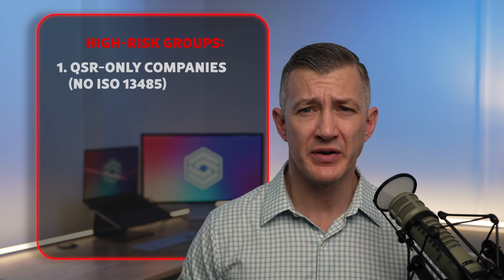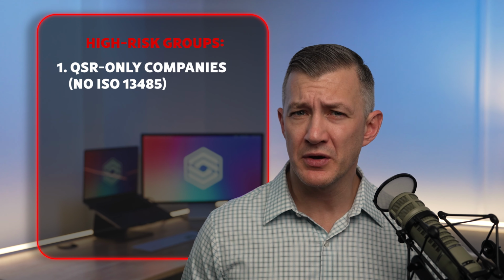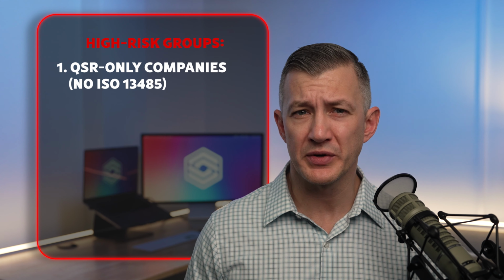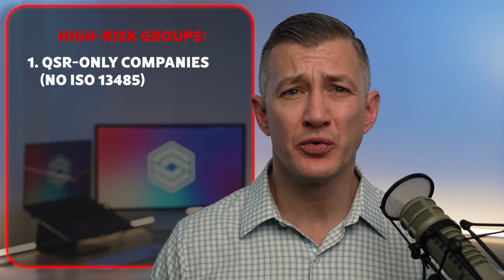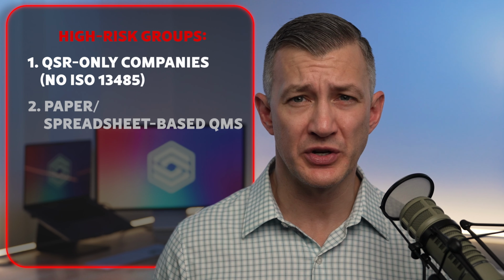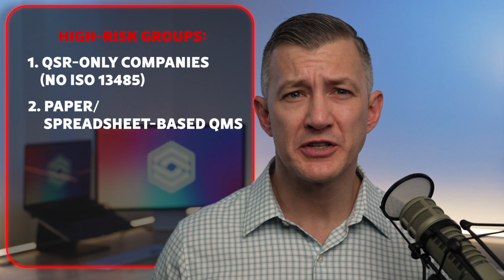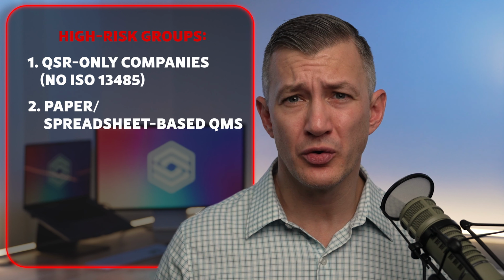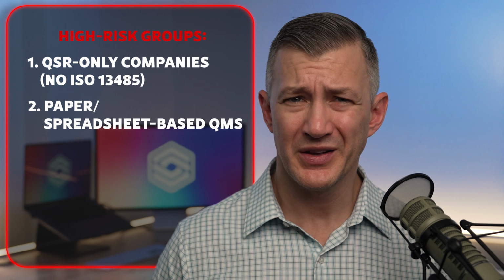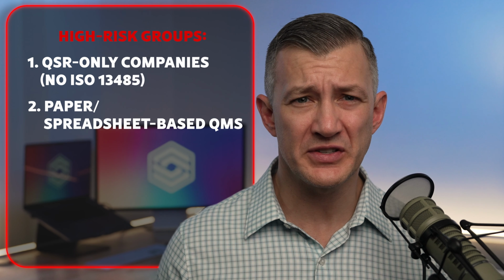So the question becomes, who's most exposed? The most high-risk manufacturers are those who only complied with QSR and never pursued ISO 13485. These companies will definitely need to restructure their quality processes to meet these standards. The other high-risk group? Businesses still running quality processes on paper or spreadsheets. The QMSR expects an interconnected, traceable, risk-based quality system. It's really hard to demonstrate with a folder of Excel files when an inspector is sitting across from you.